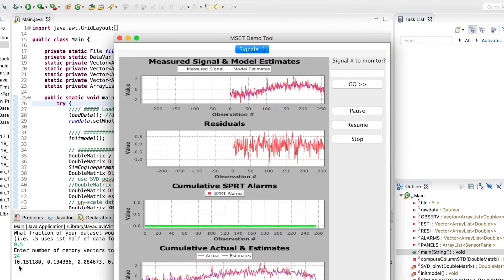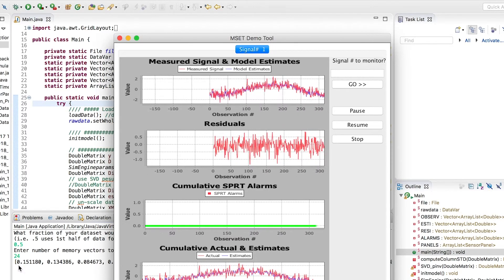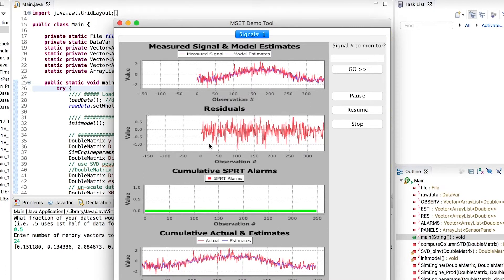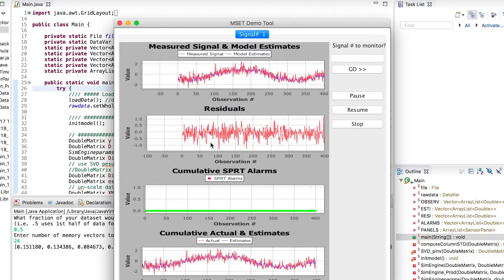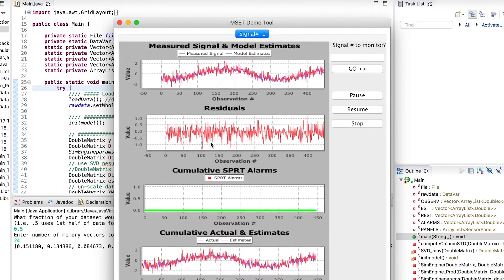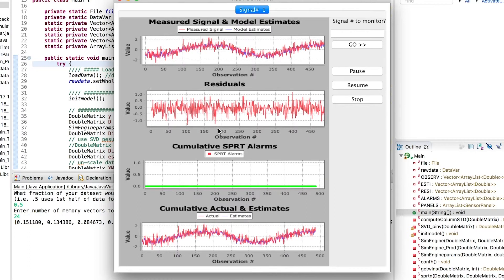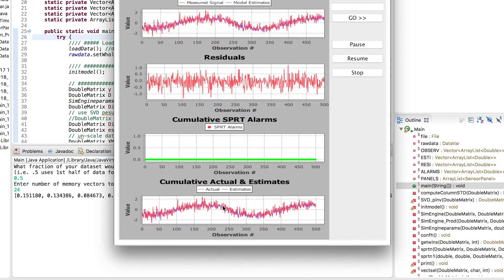The visualization shows how close the estimated values are to the actual signals. The second part of the output is the residuals, which is the difference between the actual signal values versus the estimated signal values. The third — and more important — part is the SPRT alarms, which shows if there are any alarms within a particular sensor.